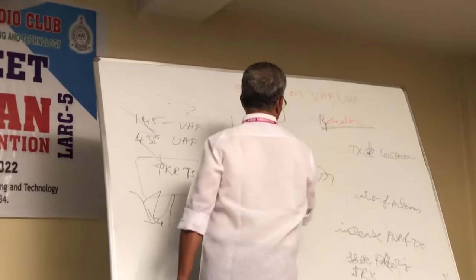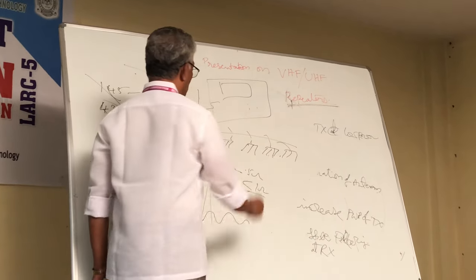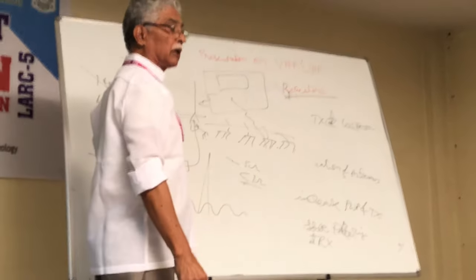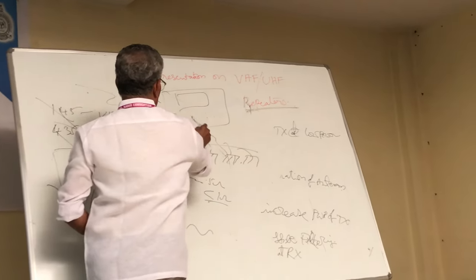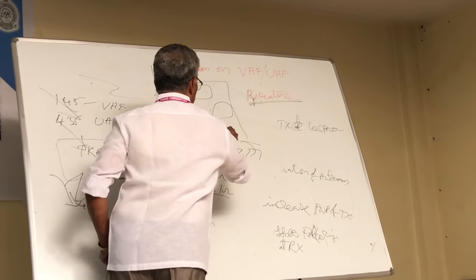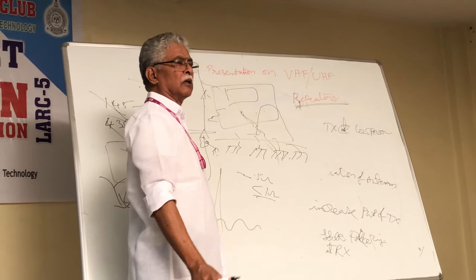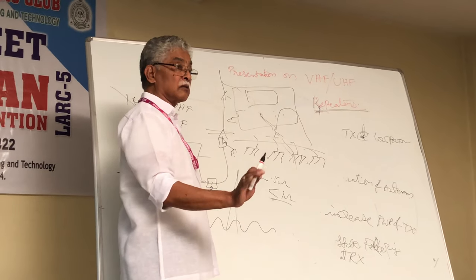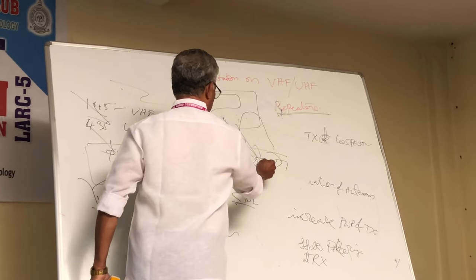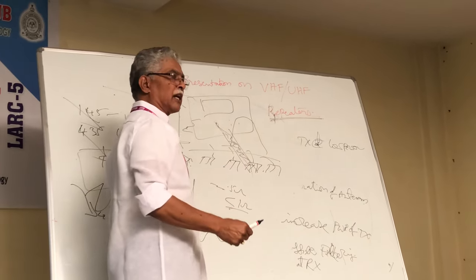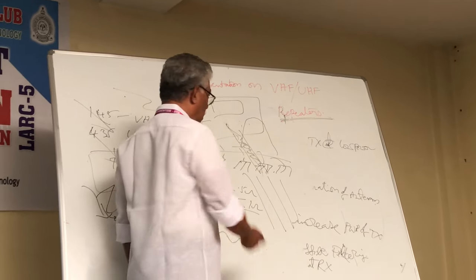You have the repeater here in a room with a grounding outside the room. Putting just one wire will not be sufficient because it has to discharge at the earliest possible in the fastest way. Whatever the discharge coming out — right now as a spike it builds up voltage of some kilovolts — that has to be discharged within milliseconds or nanoseconds. That is enough for the equipment to get damaged. That is why you need some sort of copper strips, or if not available, multiple wires in parallel to make the resistance less.